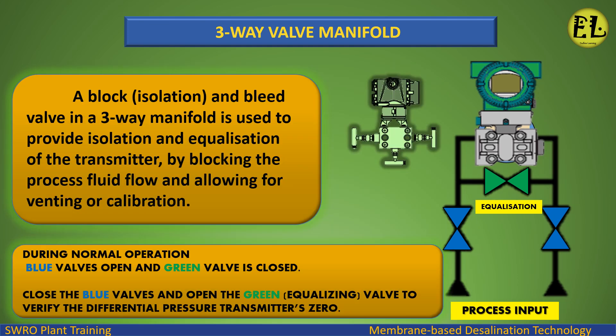A block, isolation, and bleed valve in a three-way manifold is used to provide isolation and equalization of the transmitter by blocking the process fluid flow and allowing for venting or calibration. During normal operation, the blue valves are open and the green valve is closed. Close the blue valves and open the green equalizing valve to verify the differential pressure transmitter's zero.